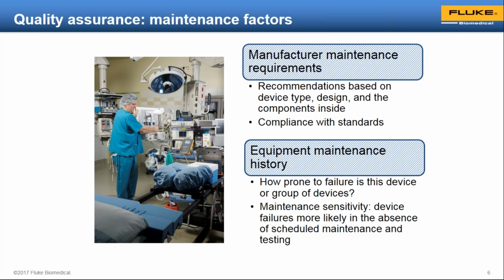We also want to take a look at the equipment history. What is its maintenance history since we've owned it, since it's been in the inventory? How prone is this device to failure or group of devices? What is the maintenance sensitivity? That is, the device failures may be more likely in the absence of scheduled maintenance and testing. All of these factors are important, and when we make good decisions by looking at this information, it helps to reduce the risk to the patient.